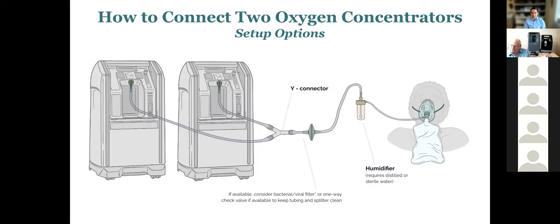Schematically, just showing number 3 in that last diagram here, we've got two oxygen concentrators. Again, the humidifier is not attached to the concentrator itself. Through silicon tubing, we're connecting to a simple plastic Y connector. Making sure that that Y connector is of adequate size to not introduce unnecessary resistance is important. From that to a bacterial viral filter and or a one-way check valve, to the humidifier, and over to the patient.